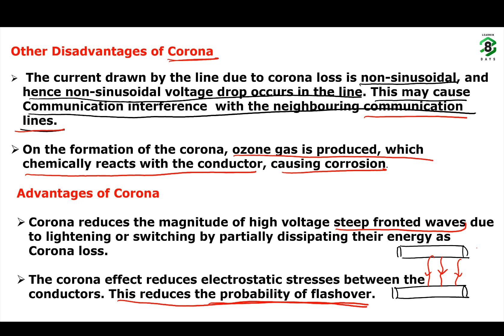And salient points of corona. Corona losses can be reduced by use of large diameter conductors, that is hollow conductors, bundled conductors and expanded ACSR conductors. Power loss due to corona is in the range of 1 to 2 kilowatt per kilometer. It's very less for transmission voltages in the range of 500 kV with bundled conductors. That means if you use bundled conductors, the corona loss is reduced. However, the corona loss increases rapidly in bad weather conditions, that is moist weather, frost conditions, ice loading conditions and heavy rains.